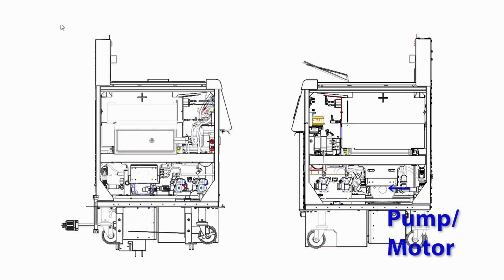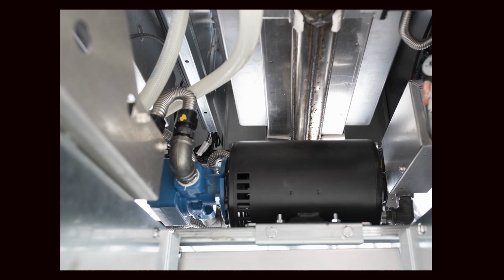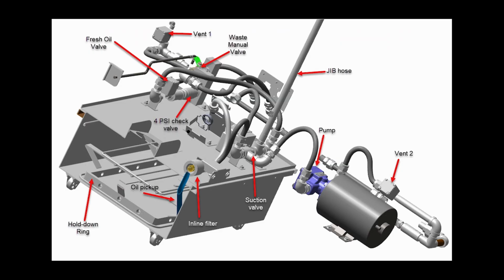The pump and motor assembly is above the SCB. It's mounted on a pivoting bracket that makes access easy. The pump is seen here connected to the top-off and the filtering plumbing. Here it is shown in a plumbing schematic that includes the filter pan and its internal components. Also visible are vents that open to drain the manifolds between filtering and top-off sessions, an inline filter on the intake of the pan, and the position for an optional oil quality sensor on top of the pan.